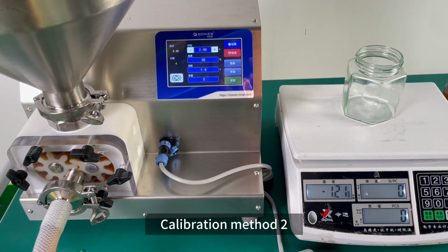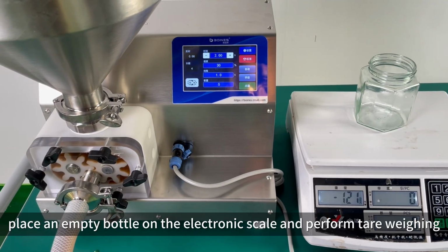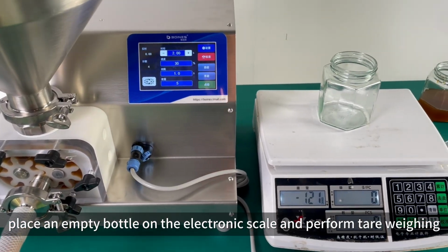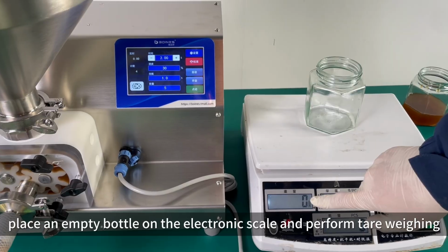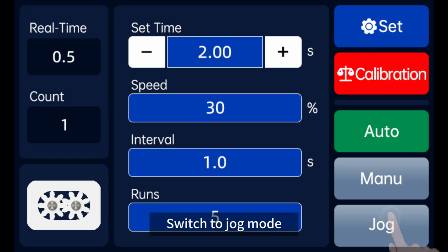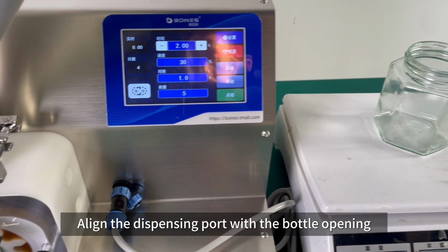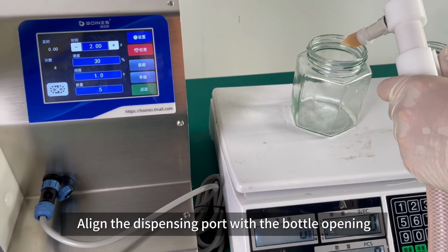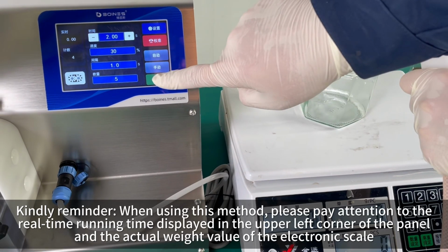Calibration method 2. Place an empty bottle on the electronic scale and perform tare weighing. Switch to jog mode. Align the dispensing port with the bottle opening. Kindly reminder, when using this method, please pay attention to the real-time running time displayed in the upper left corner of the panel, and the actual weight value of the electronic scale.